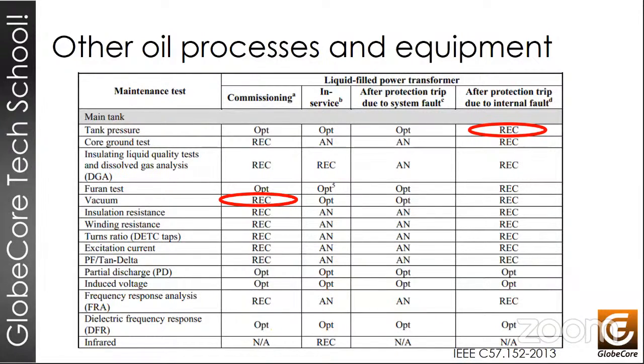So some of the processes that usually have to be done on transformers are evacuation during commissioning and creating positive pressure in transformers when the transformer is under repairs. And these processes require specialized equipment, such as vacuum units and hot air blowers. And we'll conclude this presentation by showing you some of the GlobeCore equipment that is used for these purposes. Next slide, please.